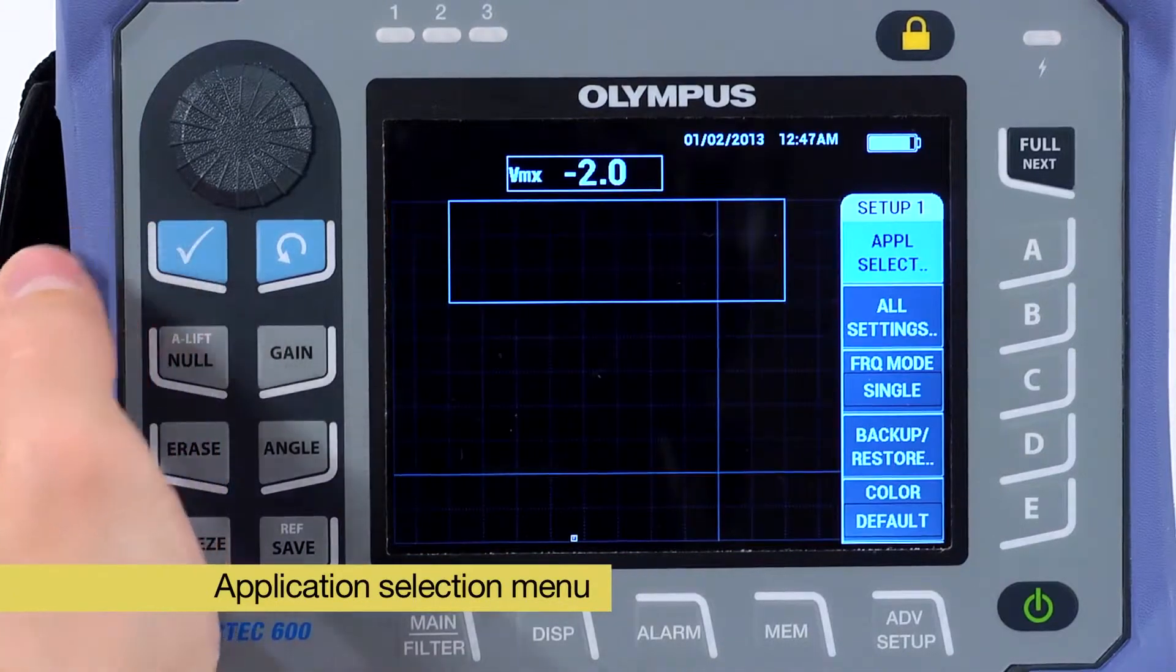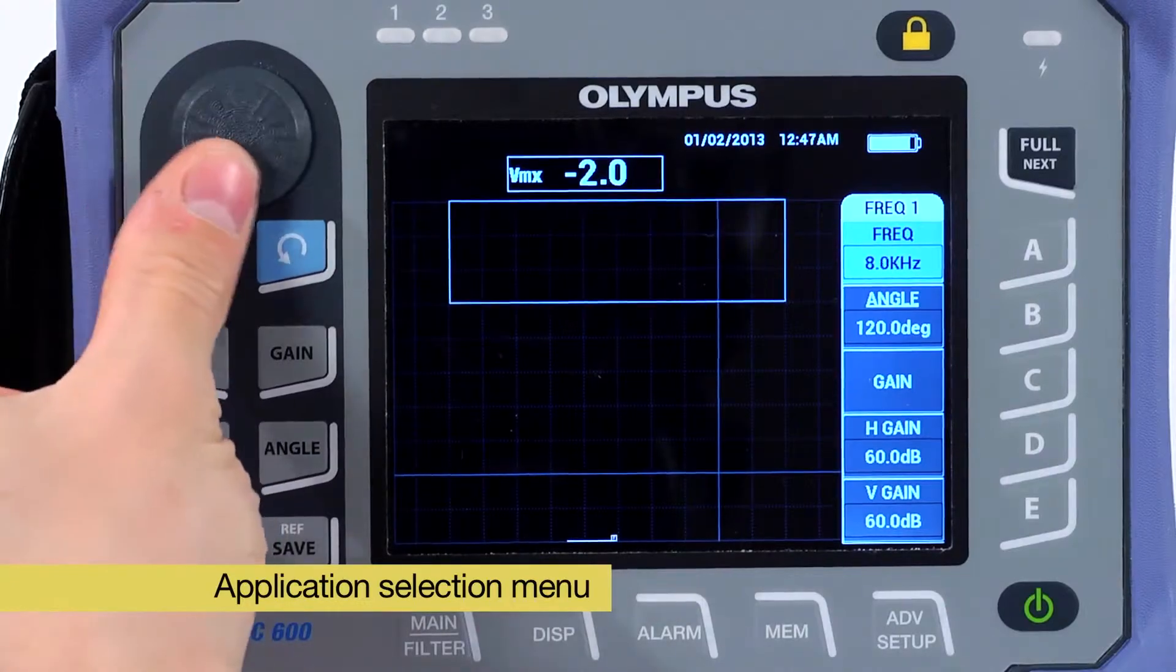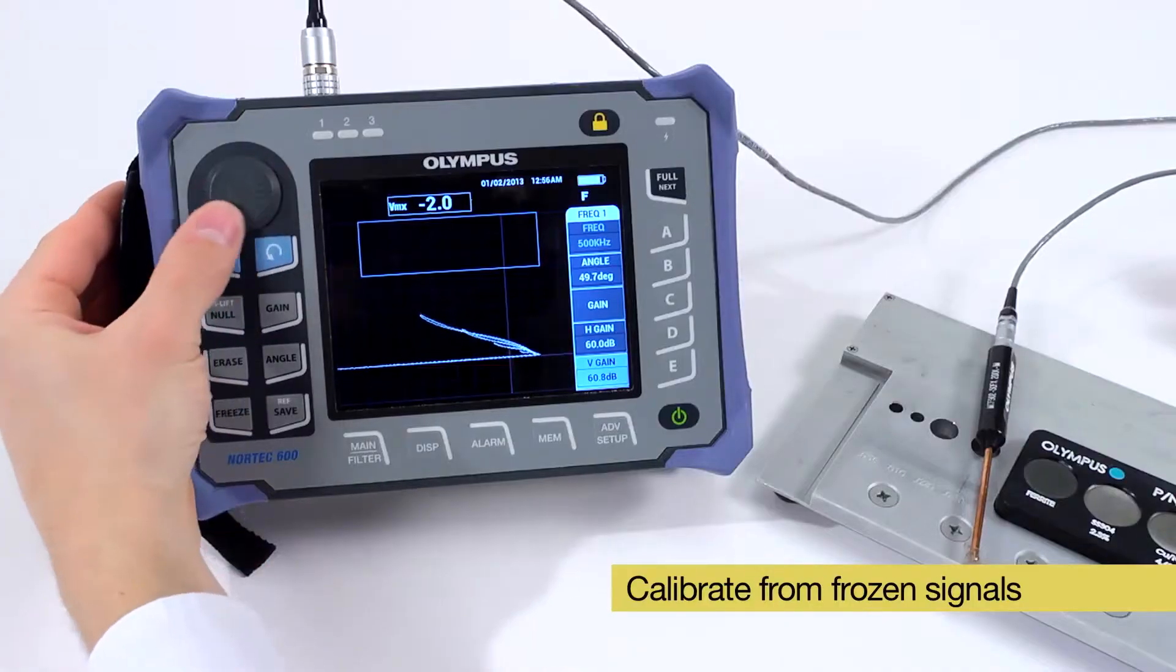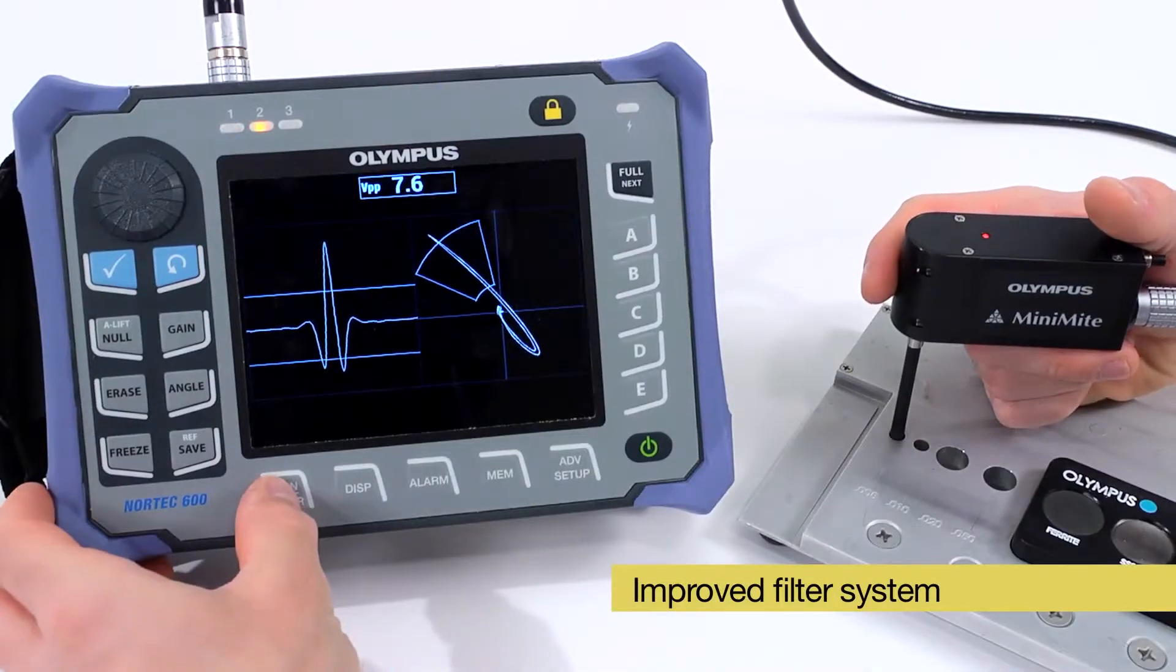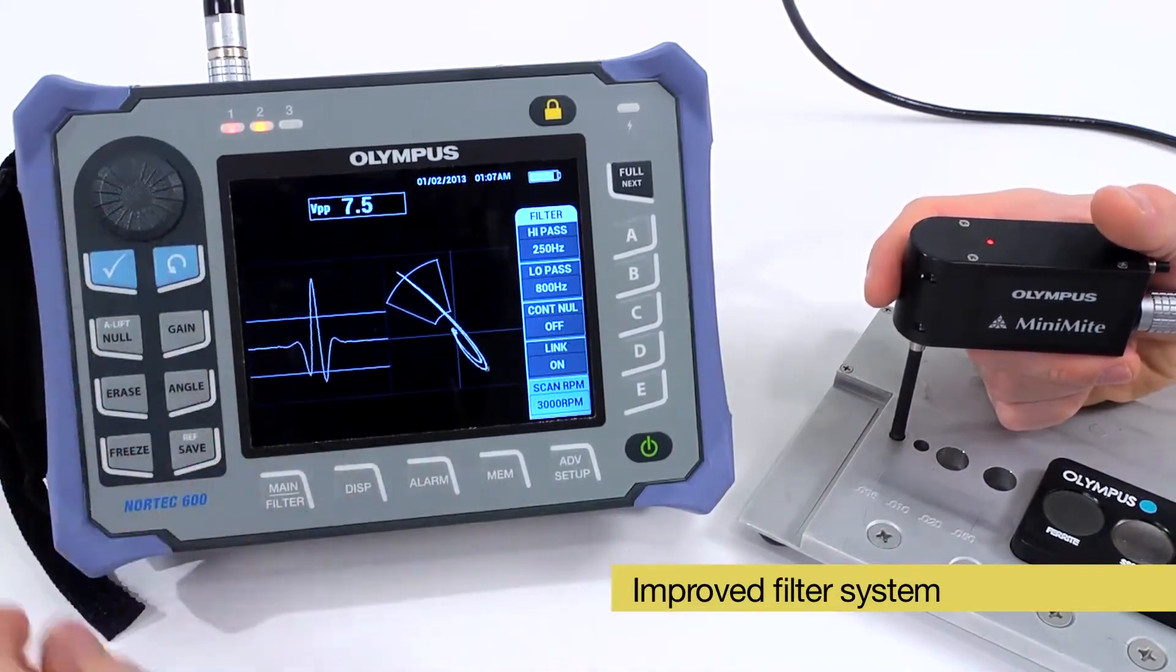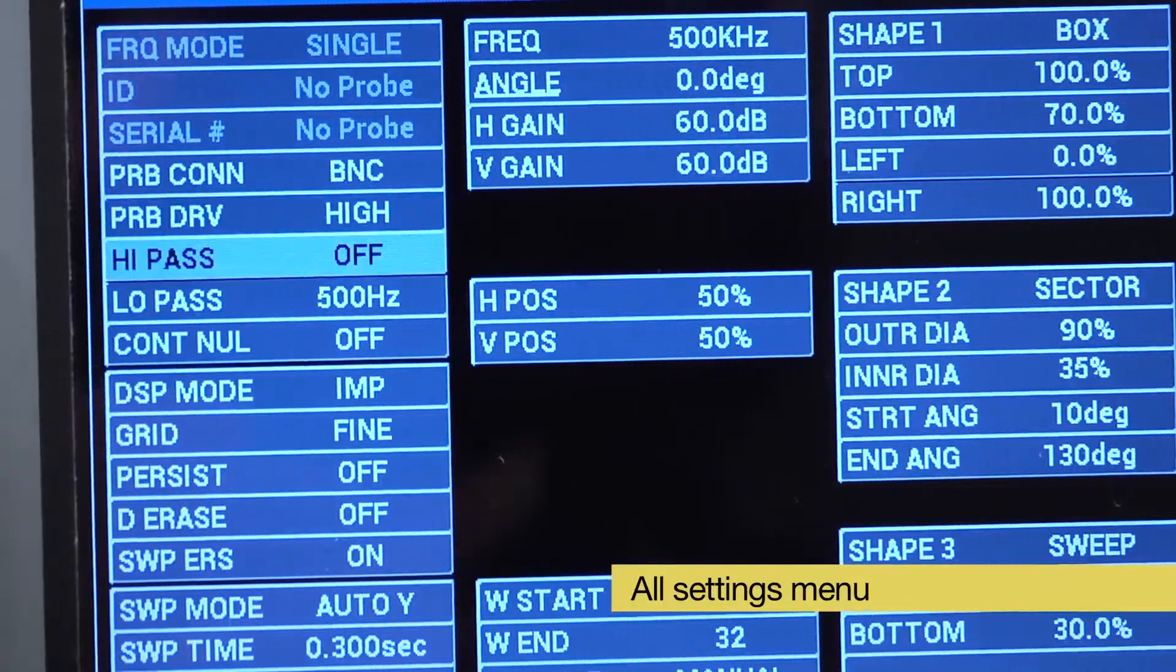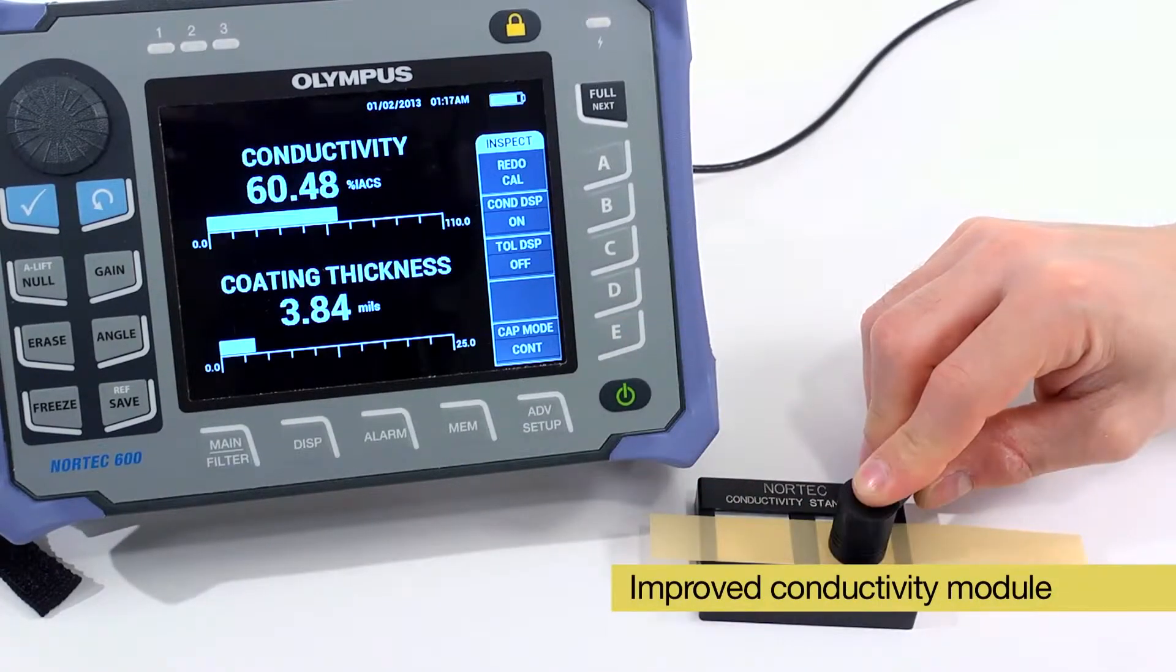Once an application has been selected, only a few parameters need to be changed in order to calibrate the signals. Other innovative features include the ability to calibrate from frozen signals which separates the scanning motion from the calibration, an improved filter system displaying standard figure eight signals for rotary scanner applications, the all settings menu which is useful to quickly configure the instrument from a procedure, and an improved conductivity module with an easy to use calibration wizard.